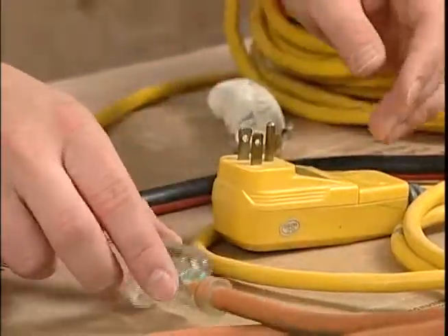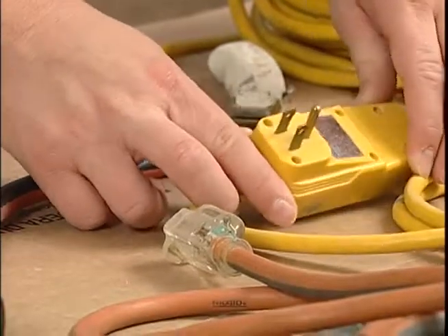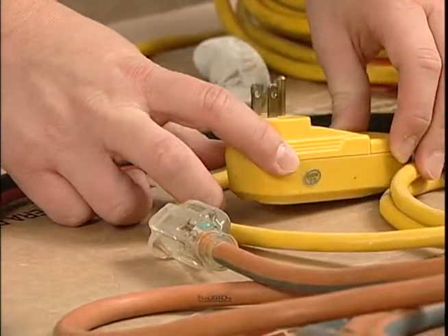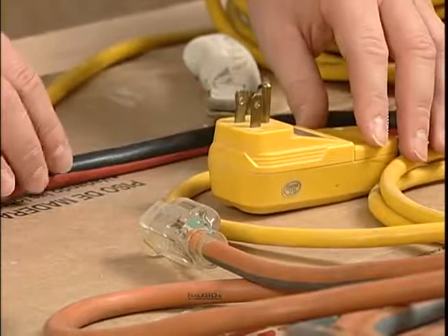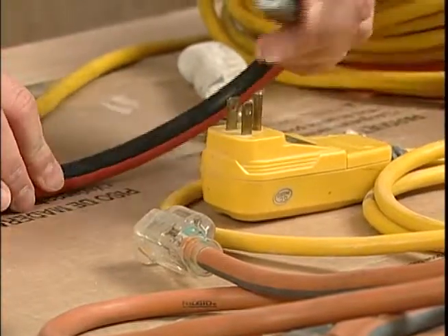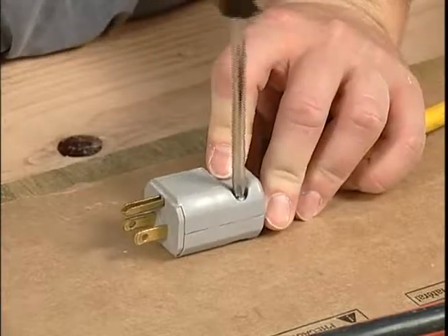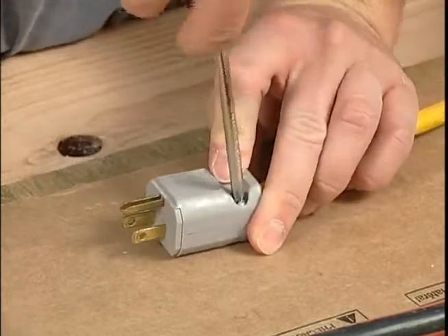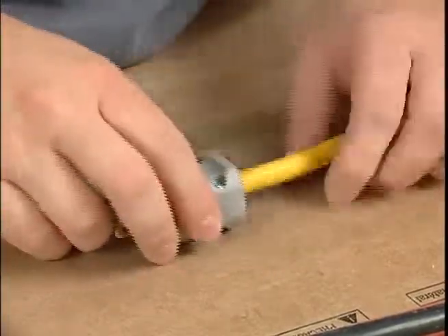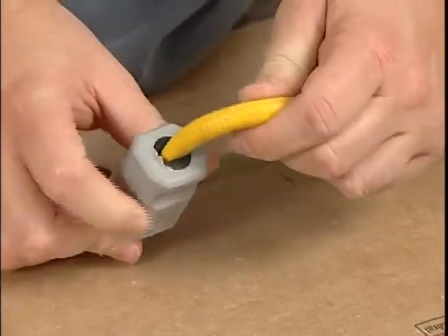All extension cords being used on the site must be 3-wire cords so that they can be grounded and can facilitate the grounding of any tools or equipment that they are connected to. Watertight or sealable connectors should be used with all tools, cords, plugs, and receptacles to limit their exposure to excessive moisture. As you can see, there's a lot employers are required to do to protect you from electrical hazards that you may encounter on a job site.